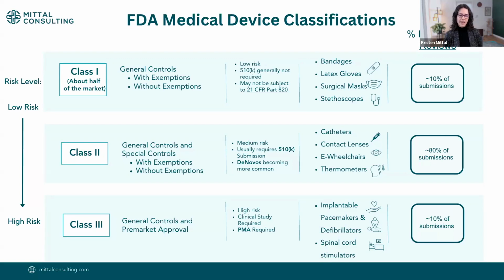And then last but not least, your highest risk type of class is class 3. De novos usually require a clinical study. Class 3 PMAs always require a clinical study. This will be a very robust clinical study because under class 3, you're not predicating off of anyone else. In the 510K world, you're basically saying there's someone else on the market who has done a lot of the heavy lifting to show safety and effectiveness, and we're basically going to repeat the same testing that they're doing, because we're almost the same as them. We're just minorly different. So we may do a minor bit of additional testing, but for the most part, we're the same, and we're going to go forward, repeating the types of testing they did.